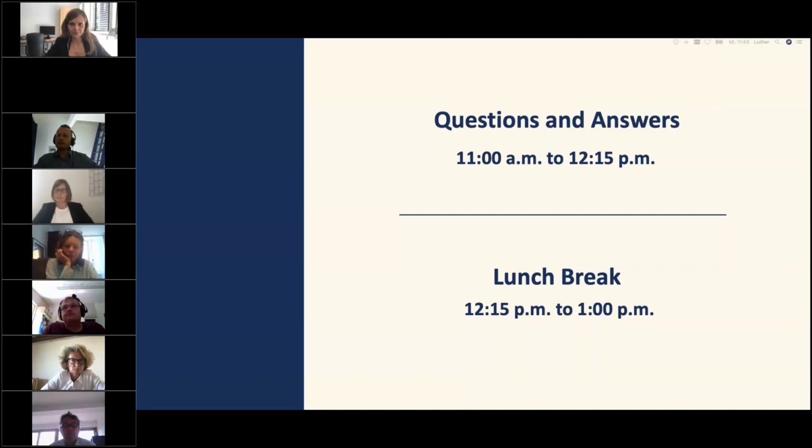There was a question regarding the software from Birgit Weisenböck concerning feature updates and bug fixes. I'd like to answer that question. In the case that your software is changed and you just do bug fixes or security patches, and you do not change the specifications of your software, so the software is not performing as specified because of the bug, you can do the bug fixing without involving the notified body, in my opinion. But Sabine Ose can state on this as well, certainly, what the notified body position is here.